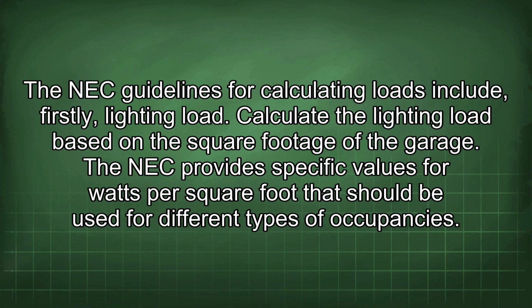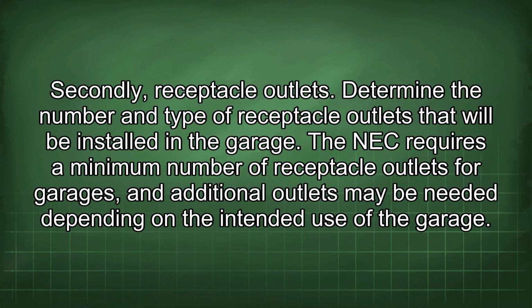The NEC guidelines for calculating loads include, firstly, lighting load. Calculate the lighting load based on the square footage of the garage. The NEC provides specific values for watts per square foot that should be used for different types of occupancies. Secondly, receptacle outlets. Determine the number and type of receptacle outlets that will be installed in the garage. The NEC requires a minimum number of receptacle outlets for garages, and additional outlets may be needed depending on the intended use of the garage.